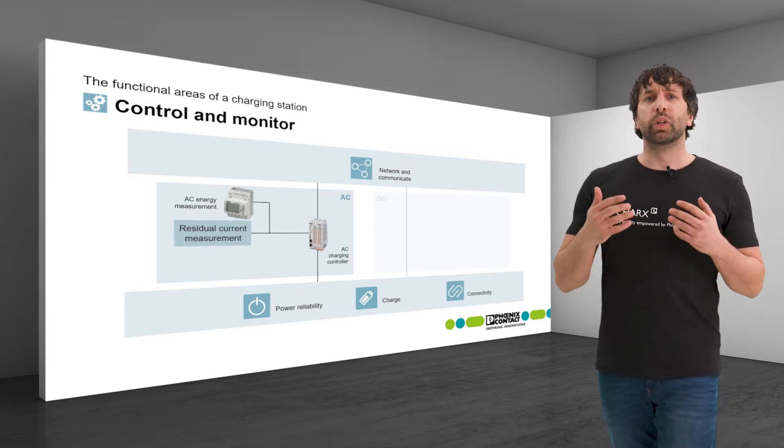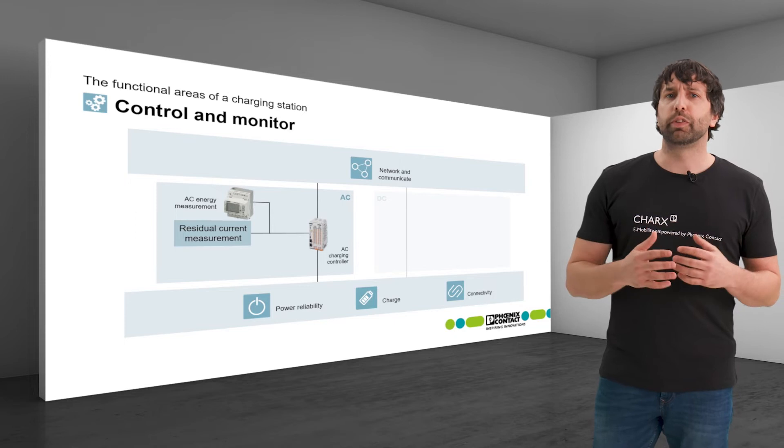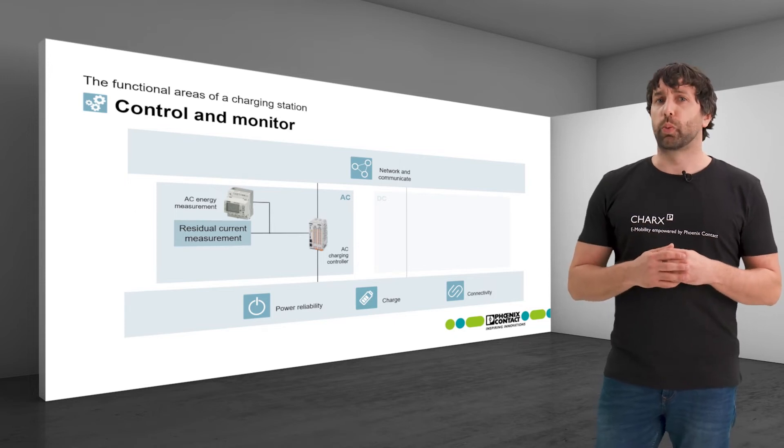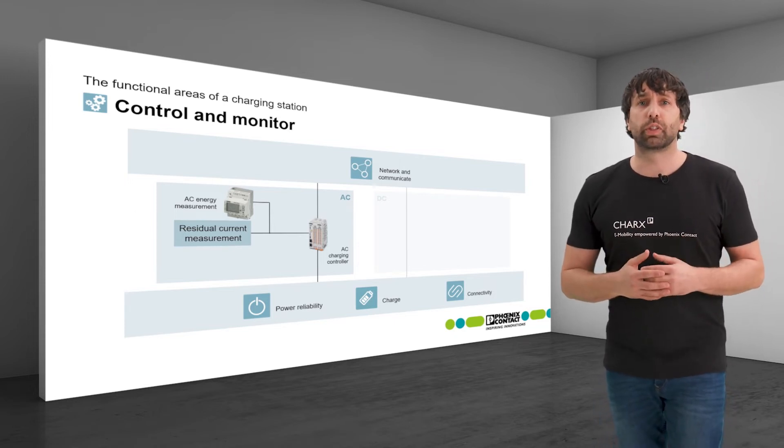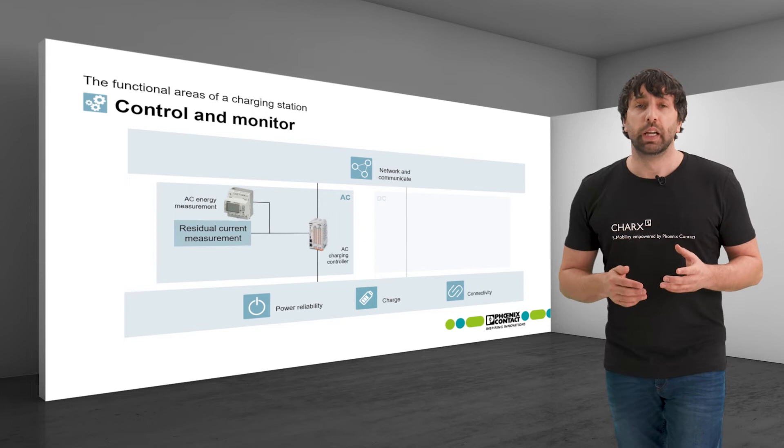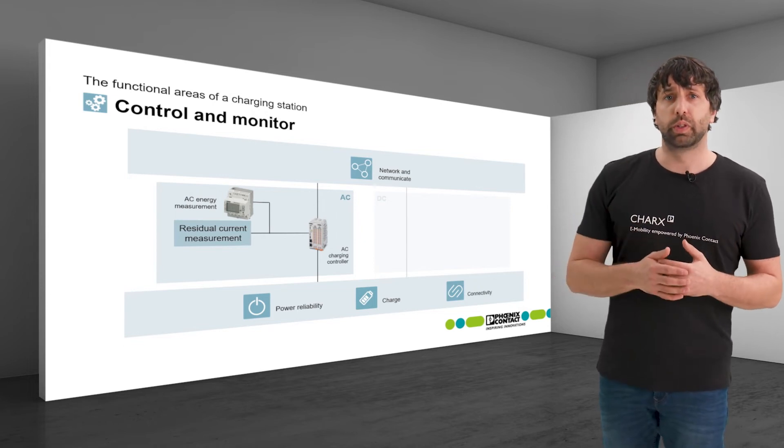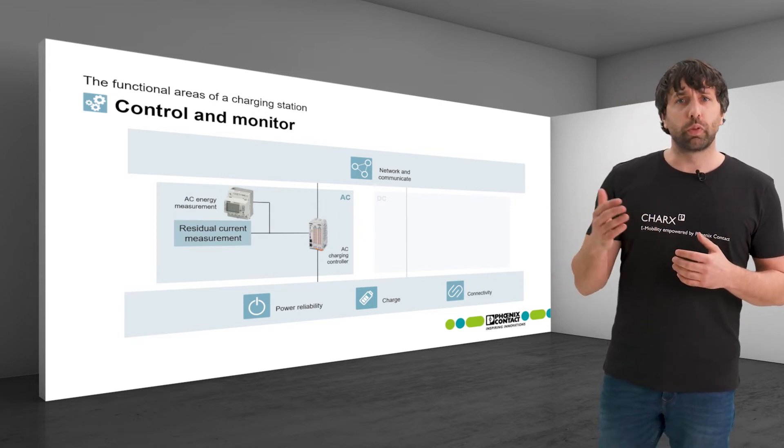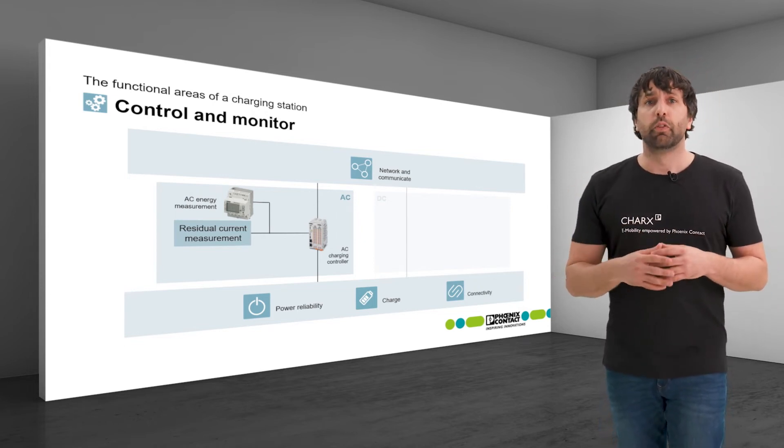A residual current measurement is a safety feature which is required by law in AC charging stations in many countries. It detects AC and DC currents which do not flow from the car back into the grid, for example due to faulty insulation.